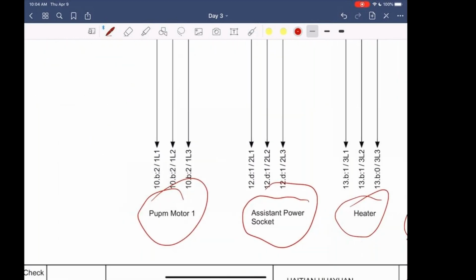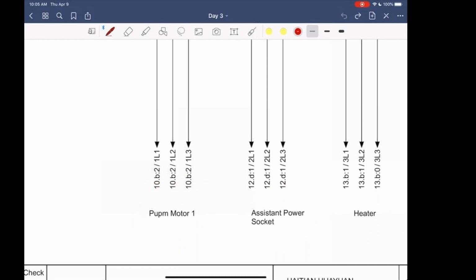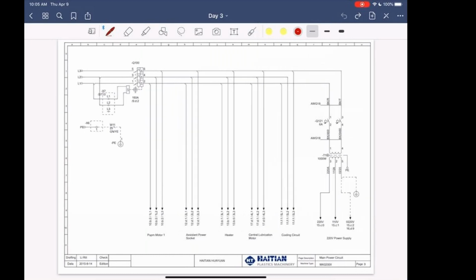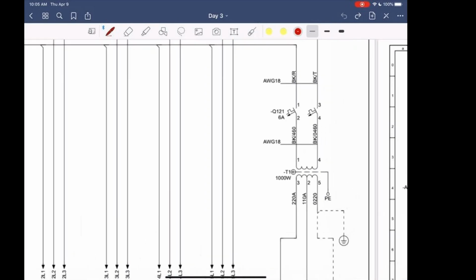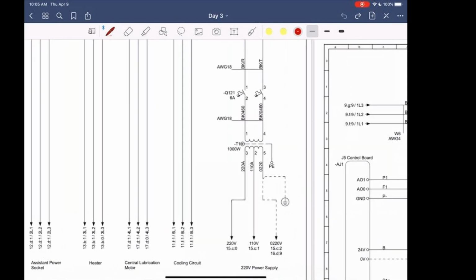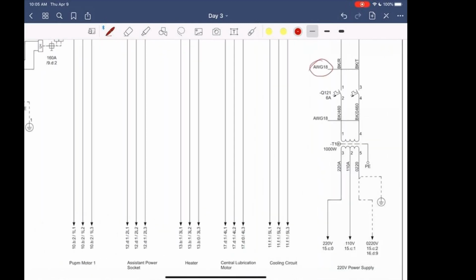To find out where these are located, it would be on page 10. B2 is the grid number. Following it over to the power supply end, it's American wire gauge 18. You're using wires R and T, and they're black wires. Goes to Q121, which is the 6 amp breaker. And that goes to this T1 transformer, which is a 1000-watt transformer.